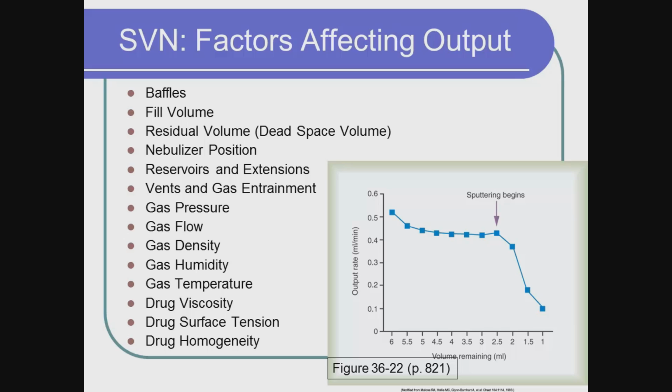And there's a lot of things that affect output of a specific nebulizer, and some of them are how much you put into it. Really, when you use these devices, you'll end up having a point in time where it actually starts to sputter. It doesn't have a smooth nebulation you can audibly hear, and patients will insist that if they just rap on the little cup, I'm going to get more out of it.